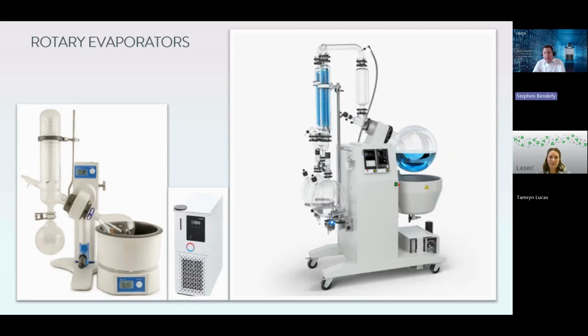Rotary evaporators are very common, and to have them connected up to a cooling water system can present some issues which are overcome when using a chilled, temperature controlled water supply. Evaporators come in different sizes, from the benchtop through to kilo lab or plant size, which may have 2 or maybe even 3 condensers if there's a trap on the vacuum line to prevent reboiling.